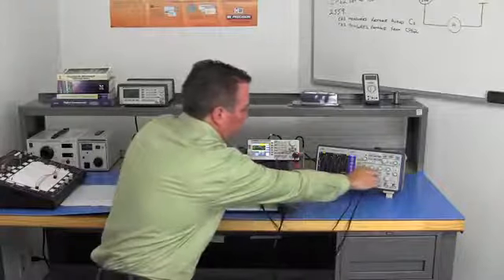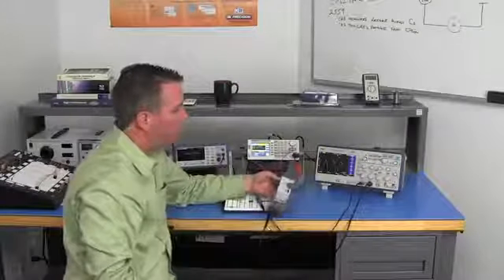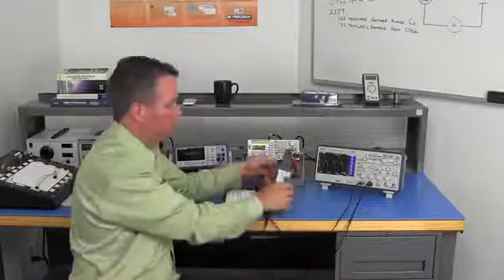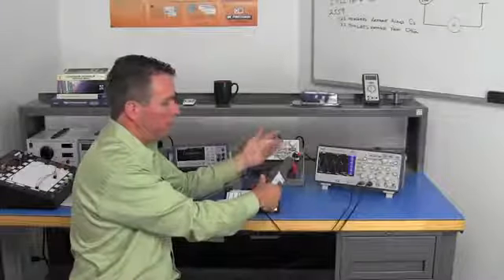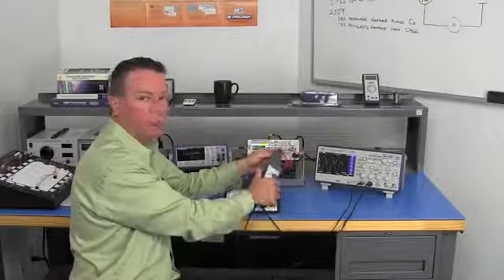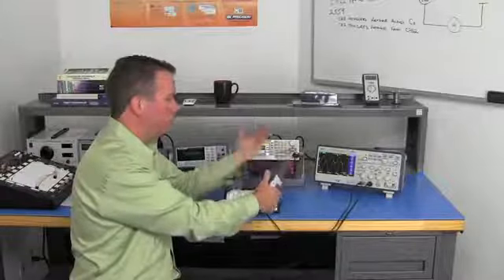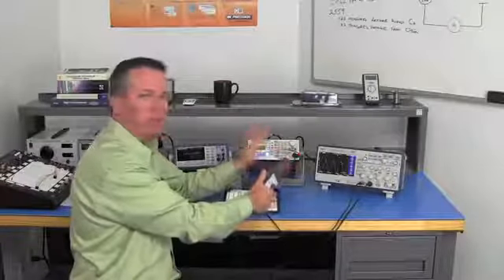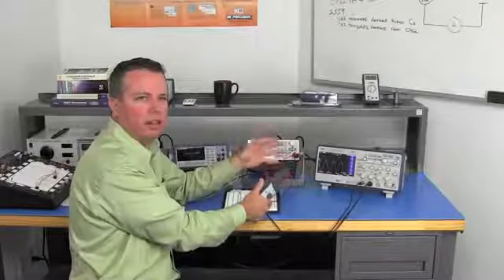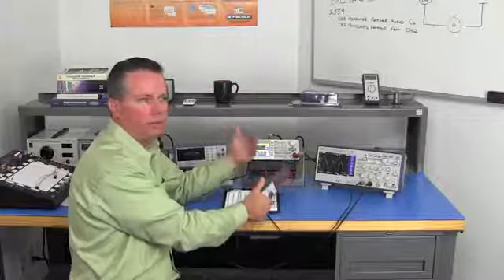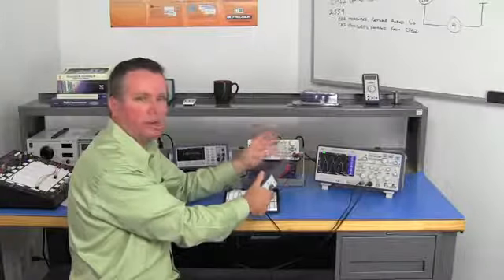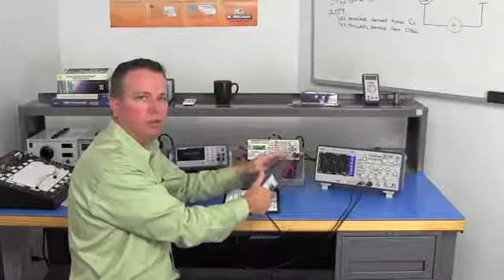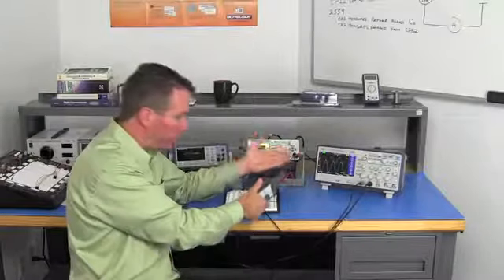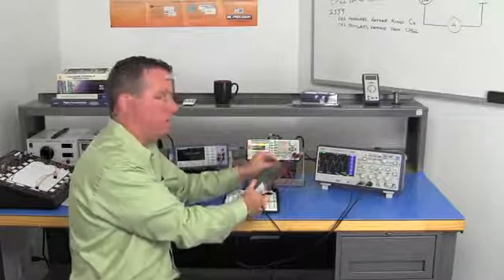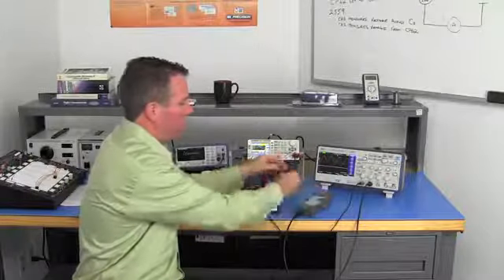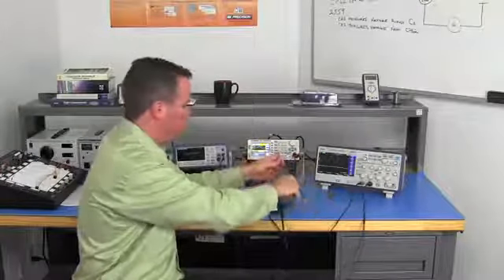Need to adjust this. So now I've got 36 millivolts. I've got 3 loops, so divide that by 3, and you've got 12 millivolts. So again, it's telling me the same value, but it's really helpful if you're measuring something a lot smaller, even down to like 50 milliamps or even less, like 10 milliamps. You could do it 5 times, and you would measure 50 millivolts here, then divide by 5, and you're able to get your actual current value.